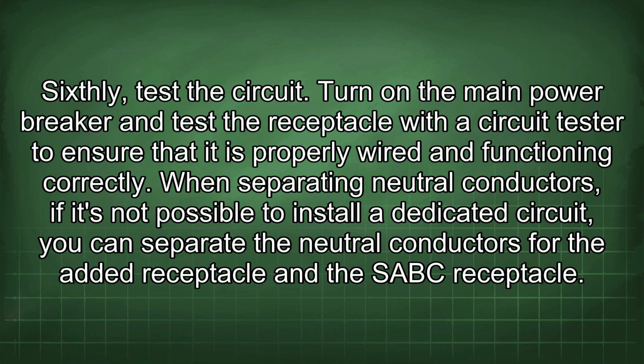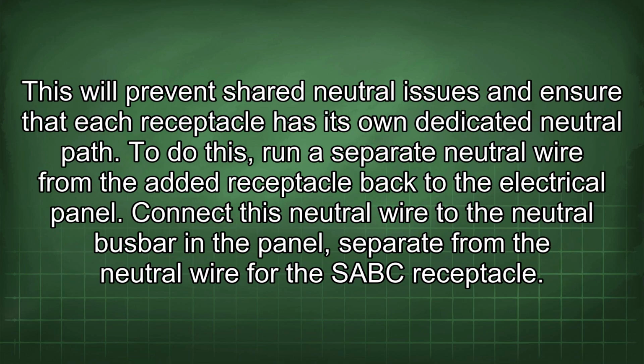Sixthly, test the circuit. Turn on the main power breaker and test the receptacle with a circuit tester to ensure that it is properly wired and functioning correctly. When separating neutral conductors, if it's not possible to install a dedicated circuit, you can separate the neutral conductors for the added receptacle and the SABC receptacle. This will prevent shared neutral issues and ensure that each receptacle has its own dedicated neutral path.